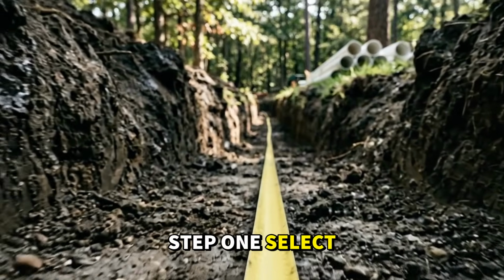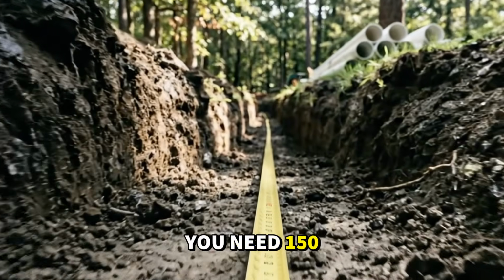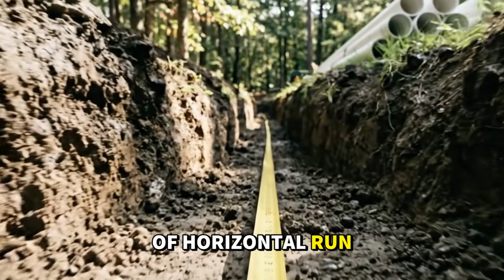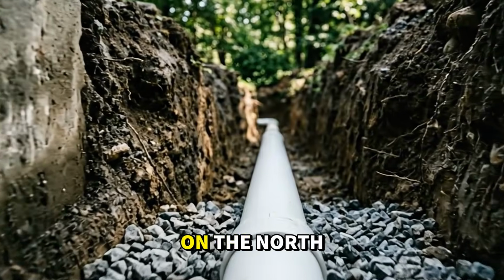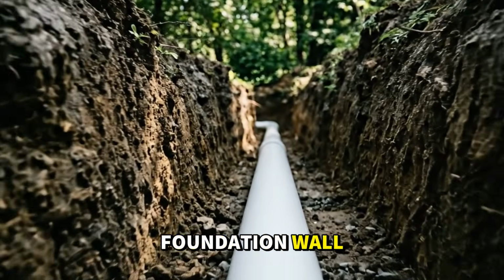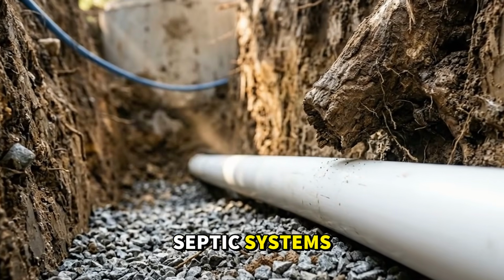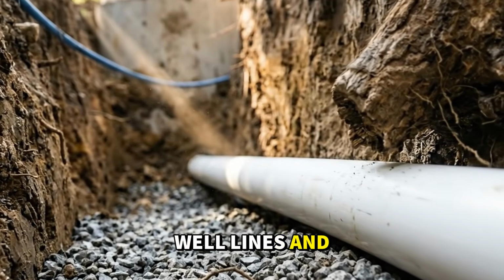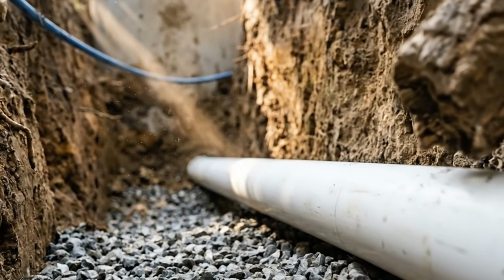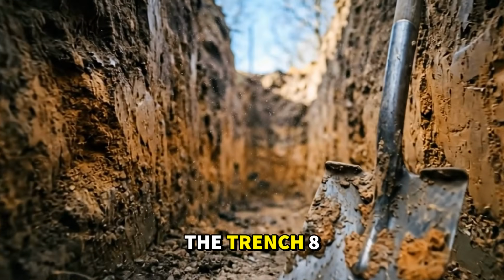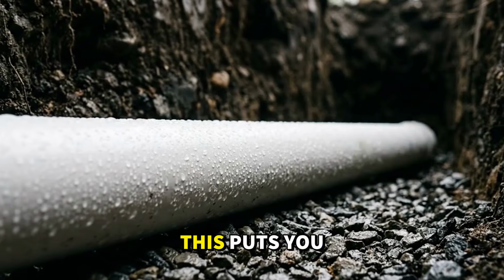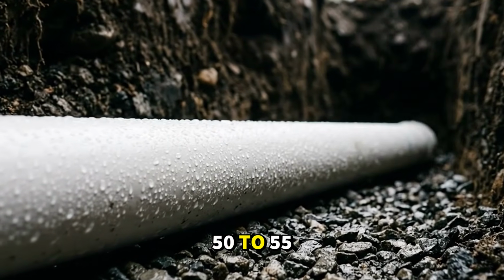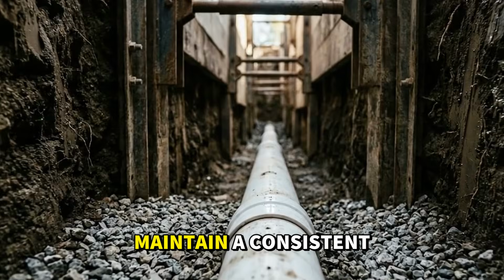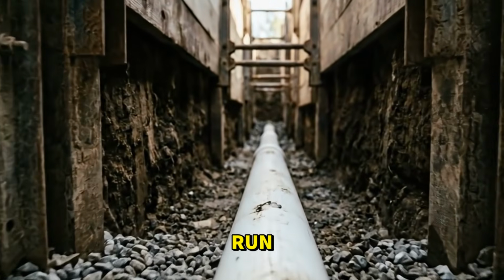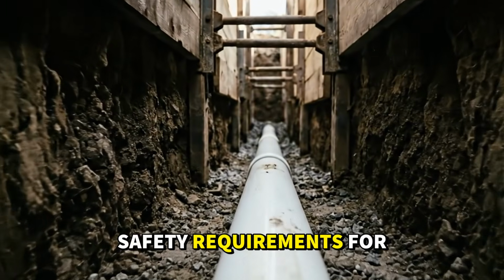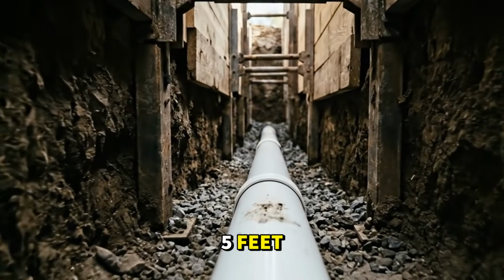Step 1. Select your route. You need 150 to 200 feet of horizontal run. The trench runs from a shaded area on the north side of your property to your foundation wall. Avoid proximity to septic systems, well lines, and large tree roots. Step 2. Dig the trench, 8 feet deep. This puts you in the stable thermal zone of 50 to 55 degrees Fahrenheit. Maintain a consistent depth throughout the run. Respect OSHA trench safety requirements for any excavation over 5 feet.